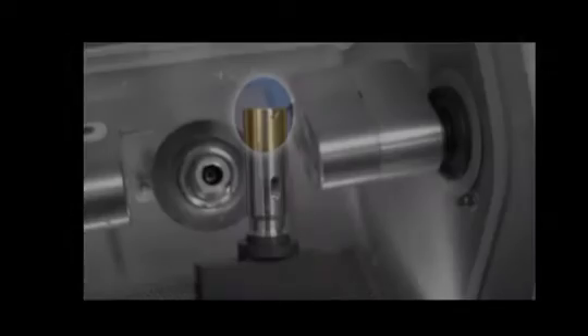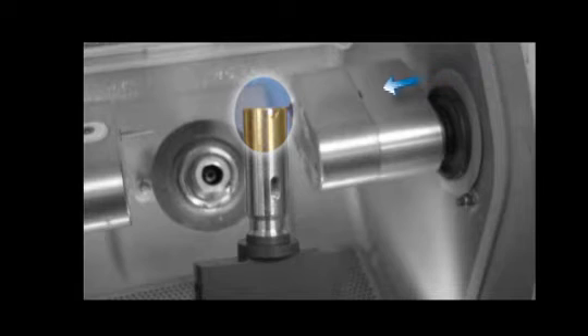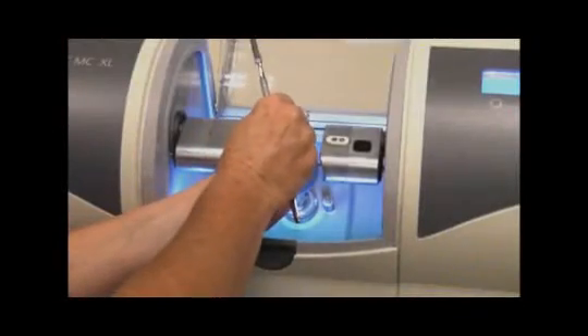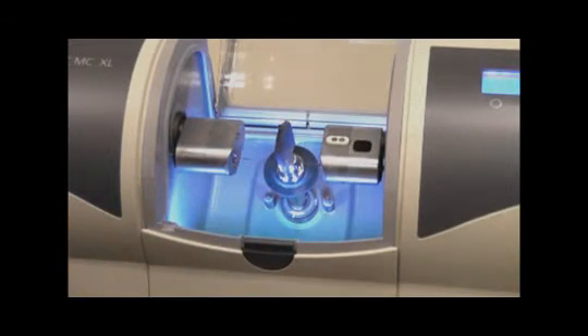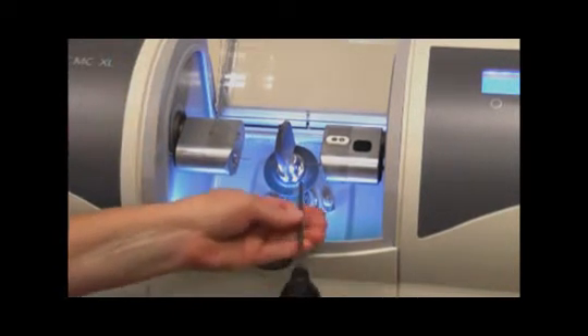There is a notch at the top of the calibration specimen that coincides with a notch on the internal portion of the block chuck. The specimen must engage this notch for it to sit down correctly. Place the calibration specimen into the block chuck with the notch facing the 9 o'clock position. Make sure that it sits flush to the chuck.